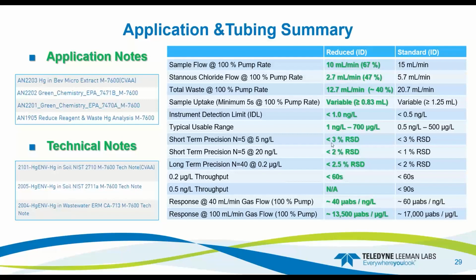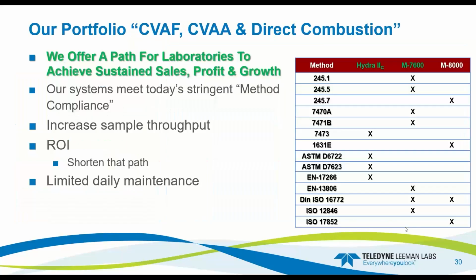So not a huge difference between that and the other tubing. Typical range changes a little bit. Precision is relatively the same. The throughput is about the same, but at 0.5 we can't quite get it because we can't get that low with this new tubing. But in all honesty, most laboratories don't run at less than 0.5 ppt anyway, so it's really a non-starter. And here's the difference in response at the different flows.